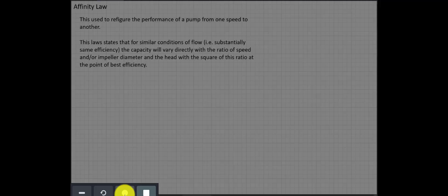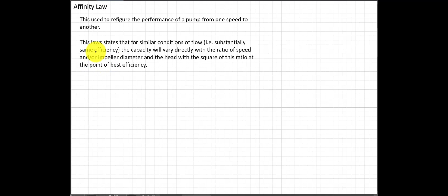Today we shall discuss the affinity law. This is used to reconfigure the performance of a pump from one speed to another. This law states that for similar conditions of flow, for example substantially the same efficiency, the capacity will vary directly with the ratio of speed and/or impeller diameter, and the head with the square of this ratio at the point of best efficiency.